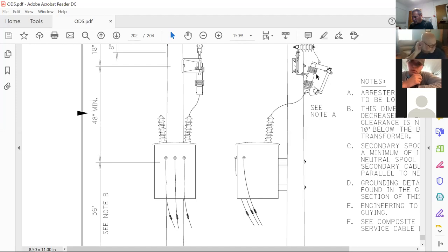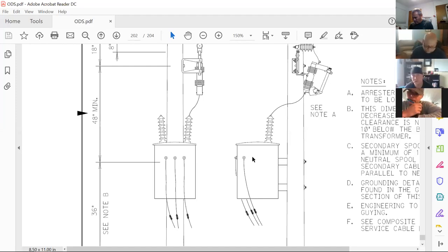Wasn't that at 100%? That's what we calculated. Right, yeah. We calculated 25 at 100%. We didn't upgrade that. We came up with a 3.4, which actually rounded up because we don't make a 3.4 amp fuse, to a 5. And like I said, Robbie's going to supply charts and kVAs of transformers.